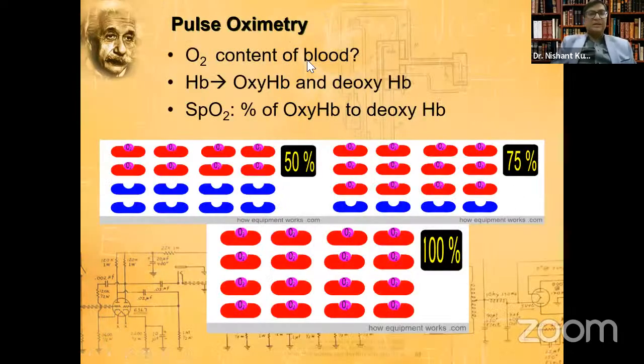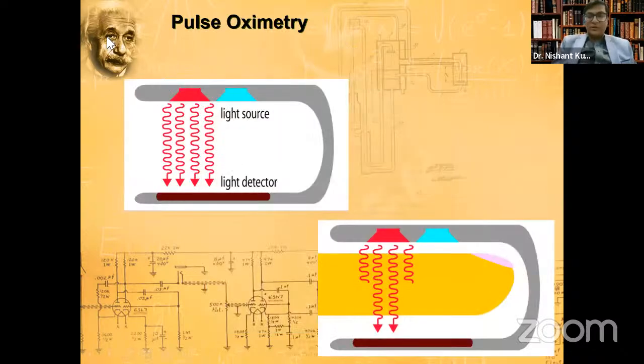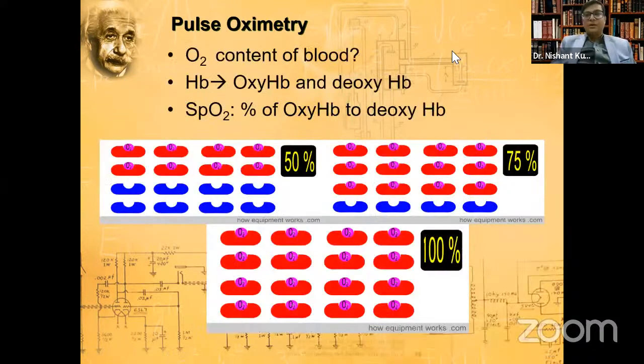Now, another important aspect is the pulse oximeter. That is one of the most important things that we use day in and day out. If not any other monitor, what we use is a pulse oximeter. So what does a pulse oximeter tell us? Does it tell us the oxygen content of the blood? Yes, in a way. It tells about hemoglobin, which is present in the oxyhemoglobin and deoxyhemoglobin form.